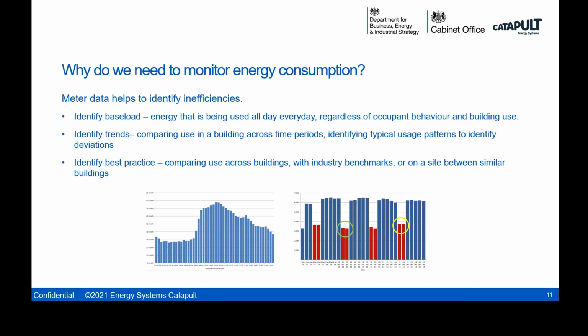There are a couple of examples here in the slide. The graph on the left shows energy data every 30 minutes, and the first third of the columns closest to the y-axis show the time between midnight and 8 a.m., when the building is closed. That might show energy used by servers, alarm systems, CCTV, some external lighting, and security staff working in the building. It's approximately 30 kilowatts, about 40% of the midday peak demand—quite a lot of energy used when the building is mostly unoccupied.